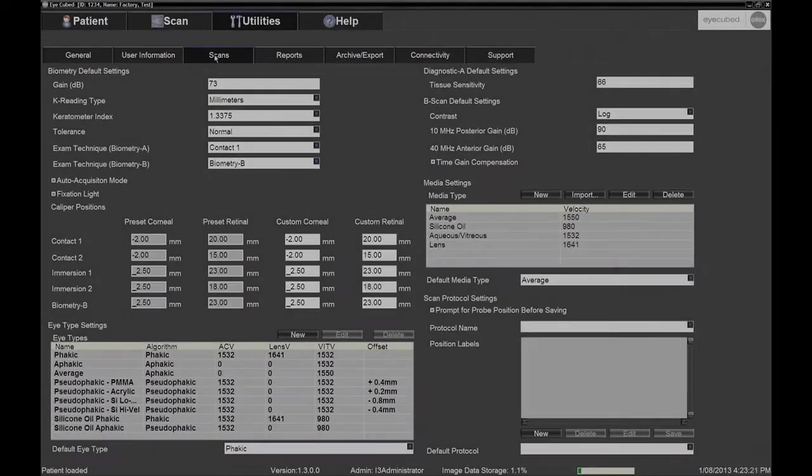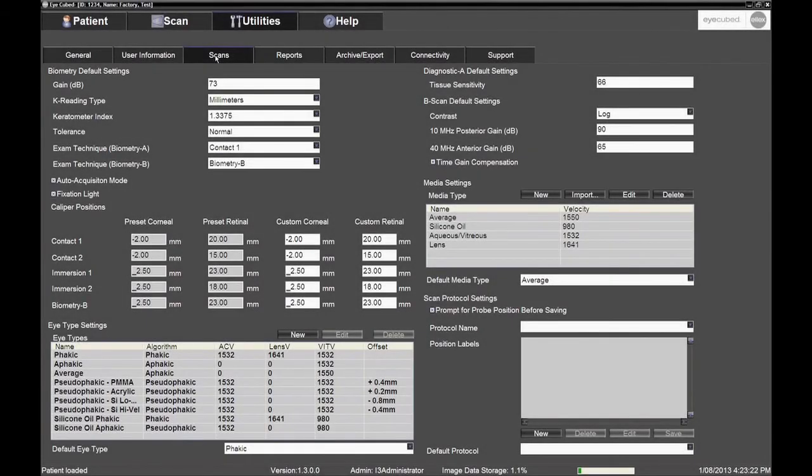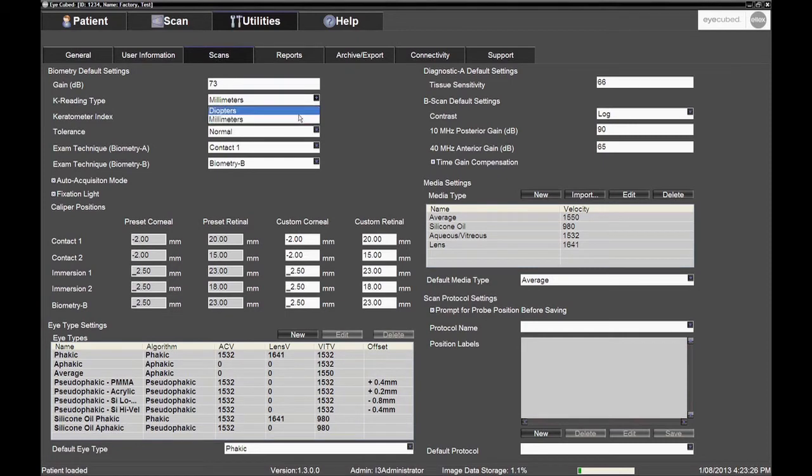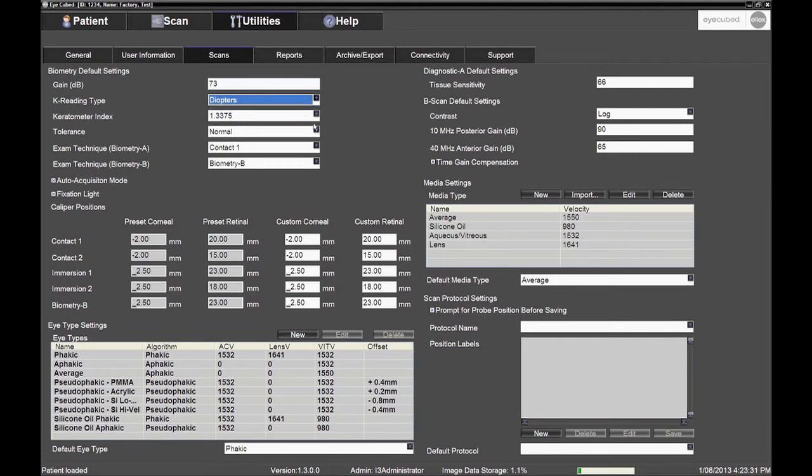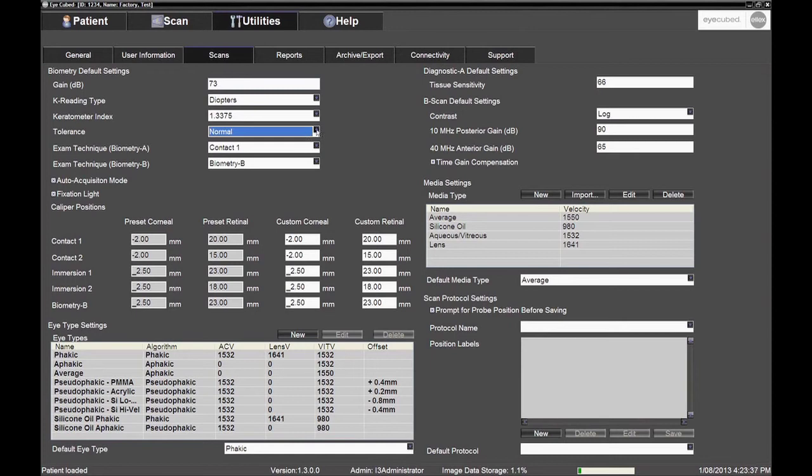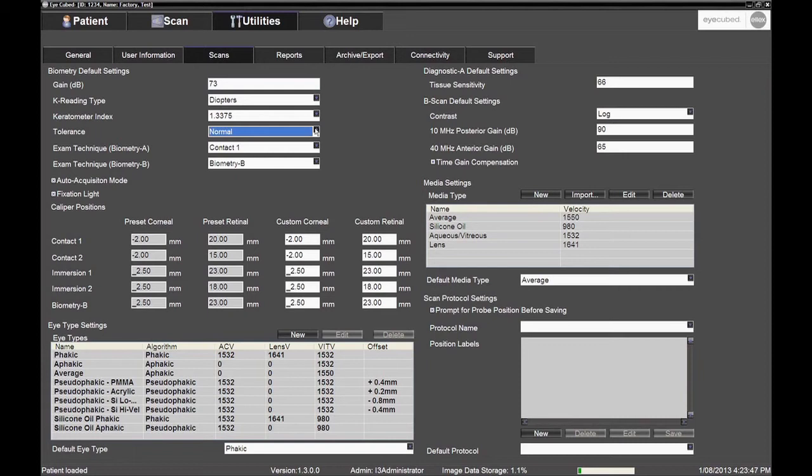Go to the Scans sub-tab to set the default settings for the biometry mode. First, make sure the appropriate K reading type is selected. Will the user enter their keratometry readings in millimetres or in diopters? Then select Normal for the tolerance, as opposed to the Expert mode.